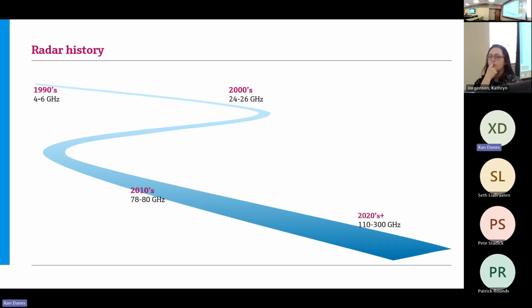It's pretty quick to observe the trends in non-contact radar measurement. Over time, not in a linear manner, the frequencies almost exclusively get higher. You might find exceptions, but looking at the major manufacturers in this space, the first non-contact radars operated between 4 and 6 gigahertz, followed a decade and a half later by what was then considered higher frequency radar in the 24 to 26 gigahertz range.